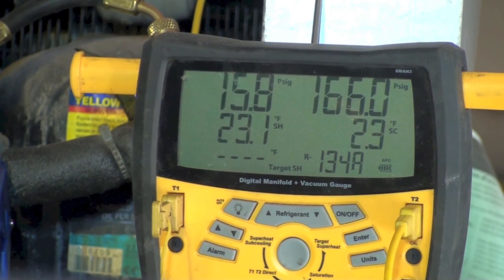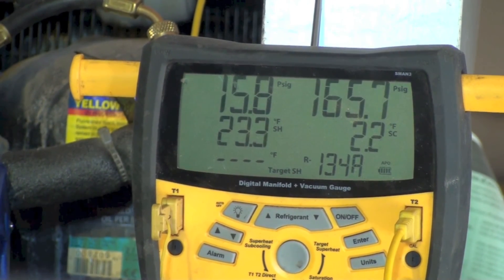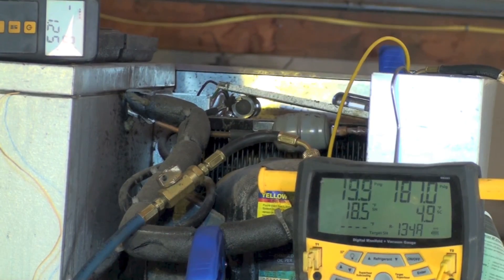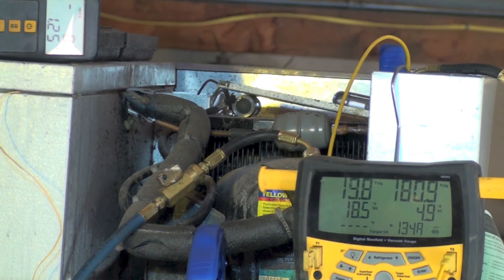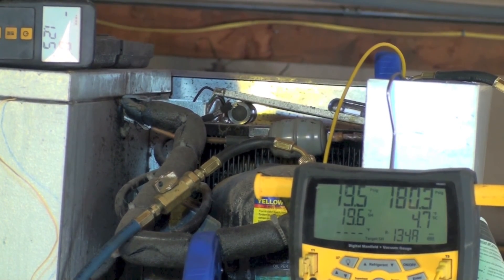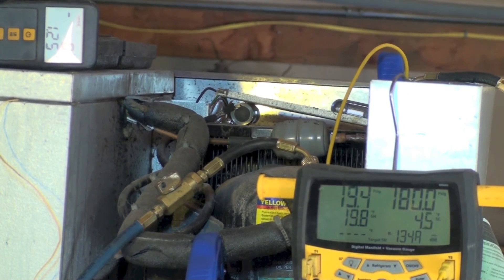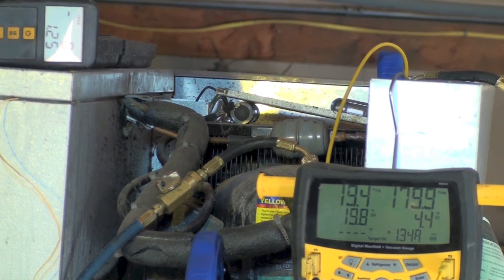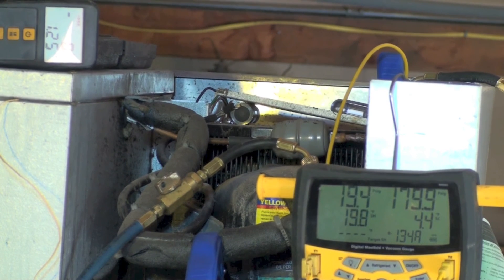Subcool is 2.4, superheat is 23. It's TXV-controlled, so obviously we're low on charge, and we're going to add a little. After adding an ounce and a quarter, the subcool went up quite a bit, and we actually saw a decrease in superheat too. What's happening is the condenser is filling up and getting to where it needs to be to provide all liquid refrigerant going into the expansion device.